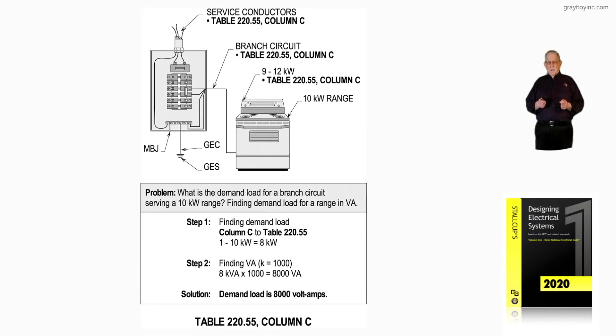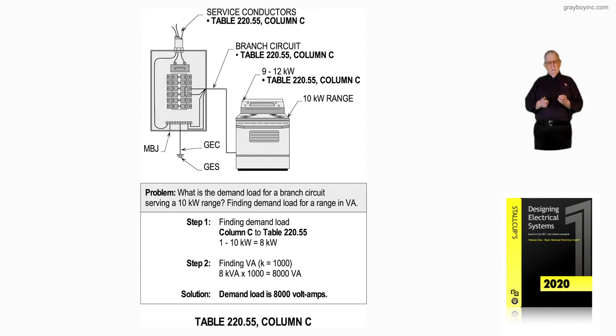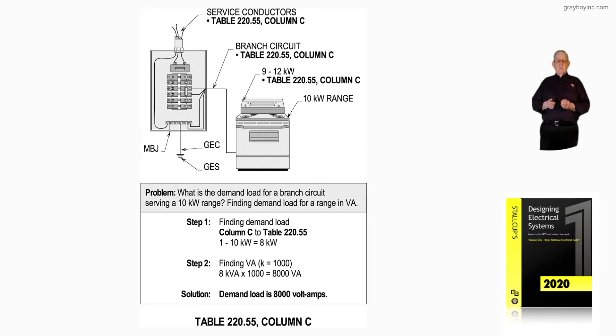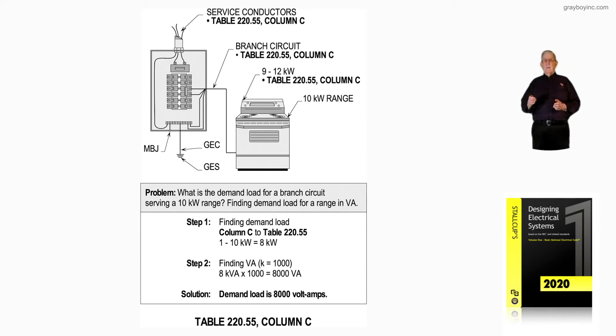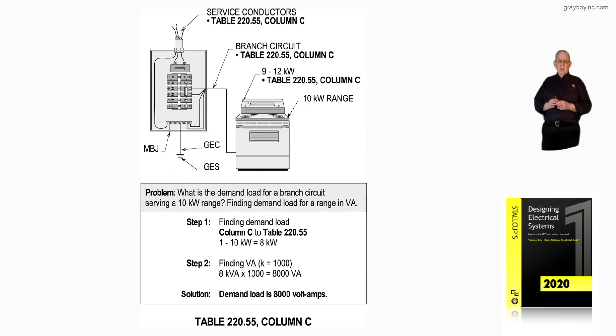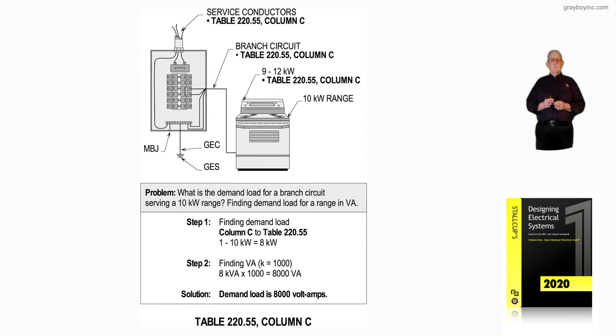We're still dealing with ranges, and this illustration covers the use of Table 220.55, Column C. Notice we have a 9 to 12 KW range here — over 8.75 up to 12 KW, not over 12 — and you can see that's a 10 KW. So as long as we fall within that range, over 8.75 KW up to 12, we can apply the question: what is the demand load for a branch circuit serving a 10 KW range? Find the demand load in VA.